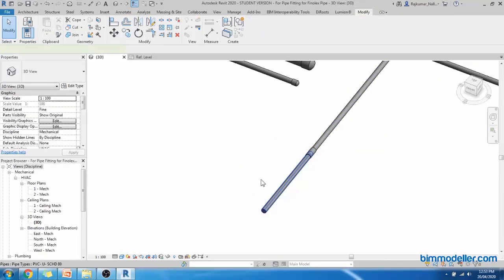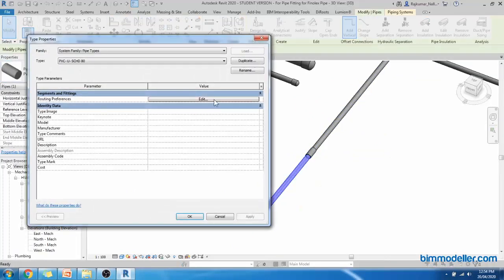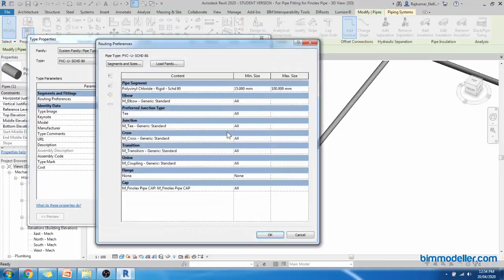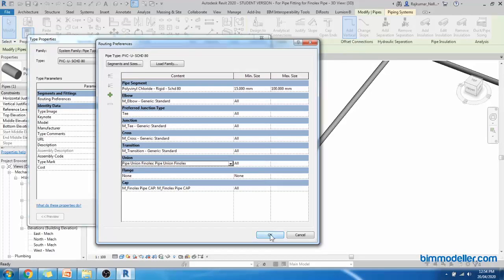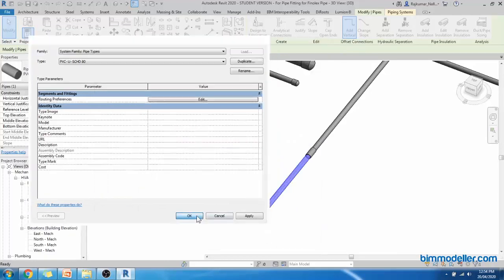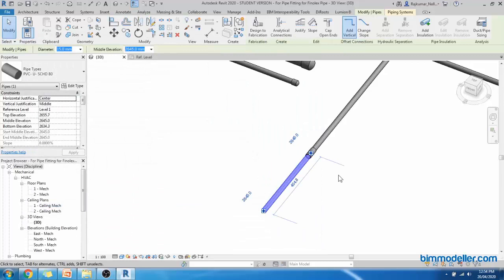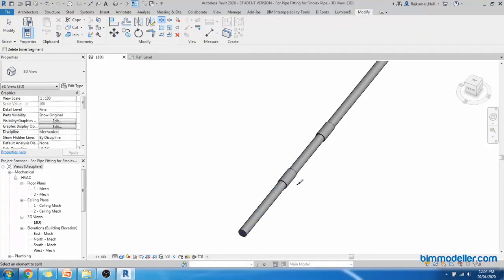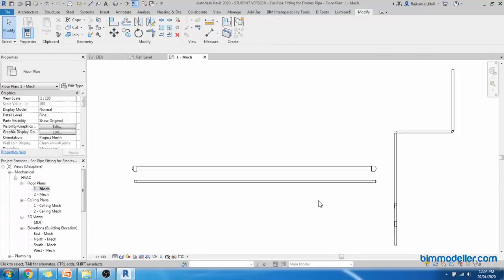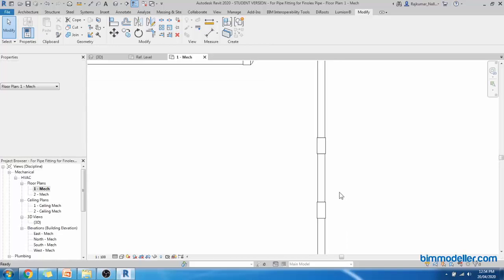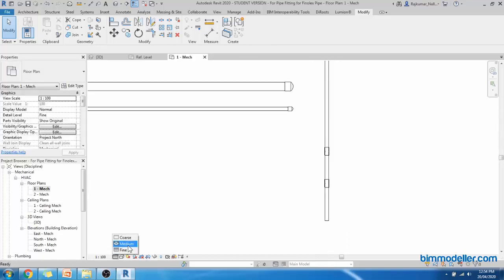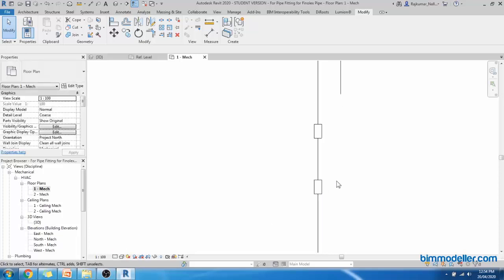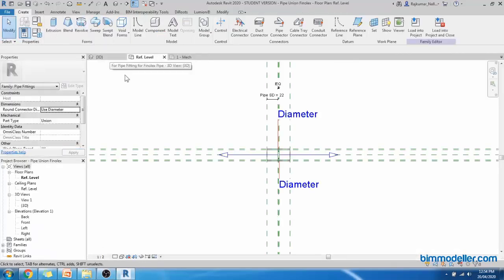You have to assign it to the routing preference. Edit the routing preference. It is nothing but union. We have to change the family. Select OK. Whenever if I do split command, I click, it assigns automatically. If I go to the floor plan again, it should show the fittings. And if I change that to coarse view, it should show the symbol not the rectangle one. So we can go back to our fittings.